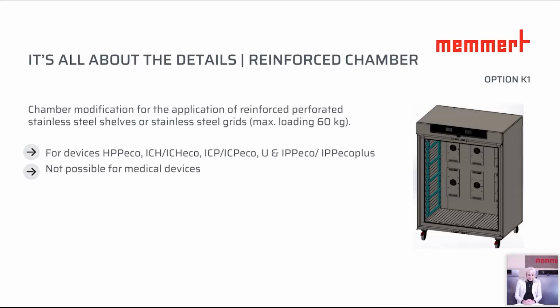Also for devices of HPP Echo, ICH Echo, ICP, ICP Echo, IPP Echo, IPP Echo Plus, this is possible, however, not for medical devices. The picture here shows the bearing rails which are mounted in the working chamber, and this means the grids are not placed in by the deep drawn ribs, but on these bearing rails, because here we have heavier loading, which also means these grids and shelves are a little bit smaller in width compared to our regular grids and shelves. The size 1060 actually has already these conditions. Let's go further to the next one.